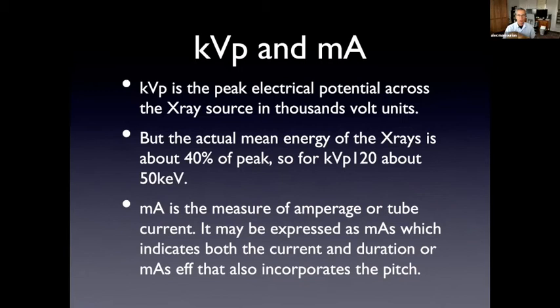KVP is a term that's used for the peak electrical potential across the x-ray source. And the P stands for peak KV. This is not the average value. The beam doesn't have a single energy. The x-ray beam actually is composed of a number of different energies. They call it a polychromatic beam. And the actual mean energy of the beam is about 40% of the peak. The MA is the measure of the amperage or tube current. This can be expressed as mAs, which indicates both the current and duration or mAs effective. That also incorporates the pitch.